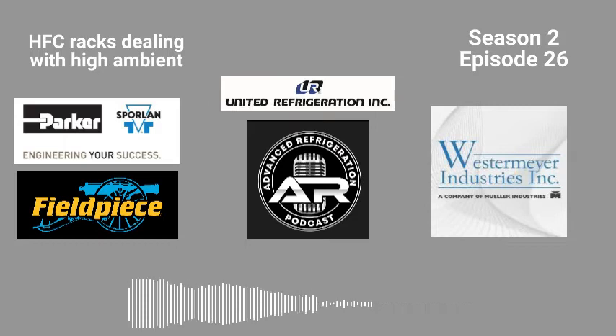All right, let's talk about something else real quick before we end this up. Guys, there's a lot of things that go into head pressure issues. Like me and Brett were talking about, a lot of it's condenser. It's not all just the condenser, too. Superheat coming back to the rack. You guys would not believe how much of a difference going from a 50-degree return gas temp to a 20-degree return gas temp or a 10-degree return gas temp makes.